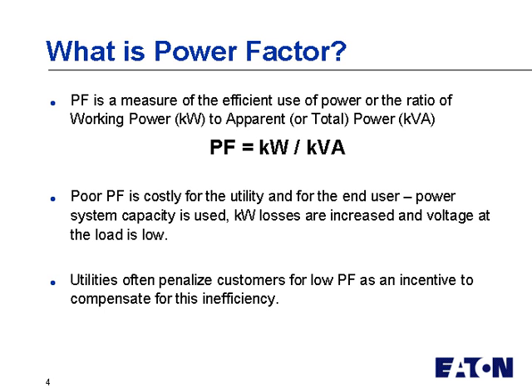So what is power factor? Power factor is really a measure of the efficiency, or the efficient use of working power versus the total power that's supplied by the utility company or by the generators that you may have on site. And so power factor is the ratio of kilowatts versus kVA. kVA is the total power that's used.